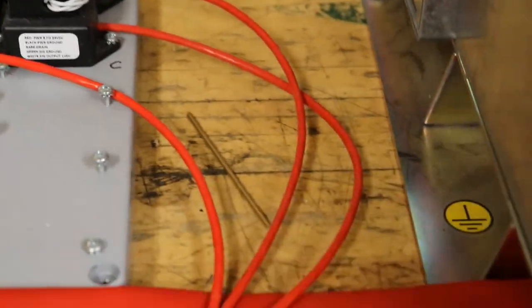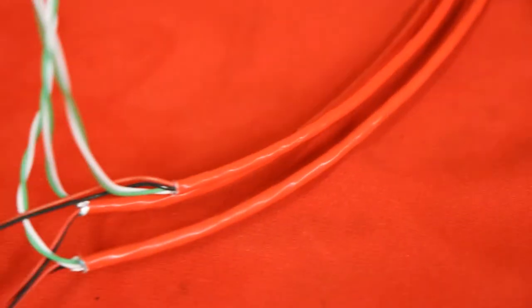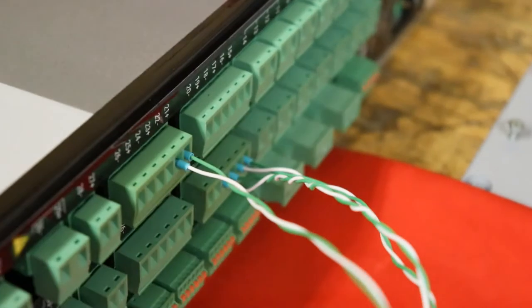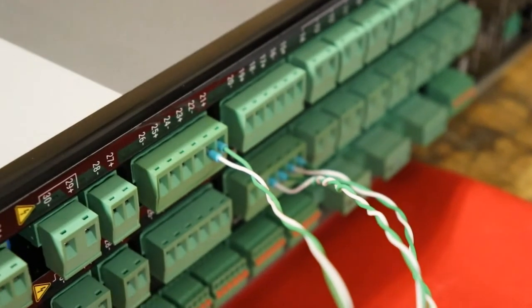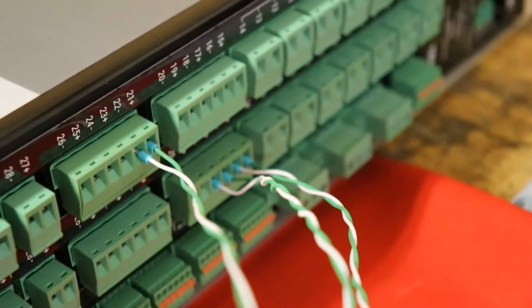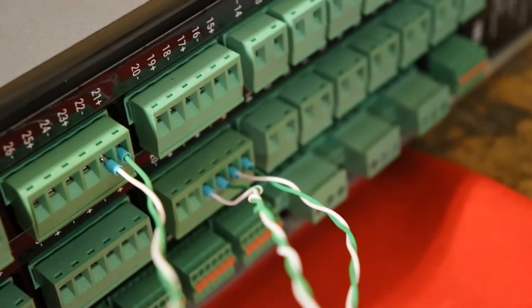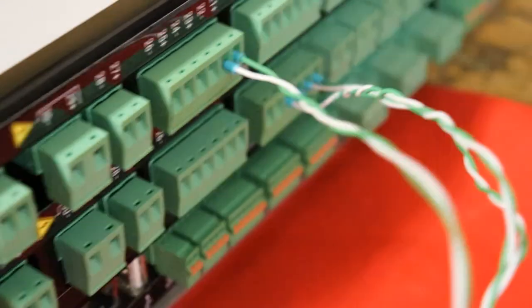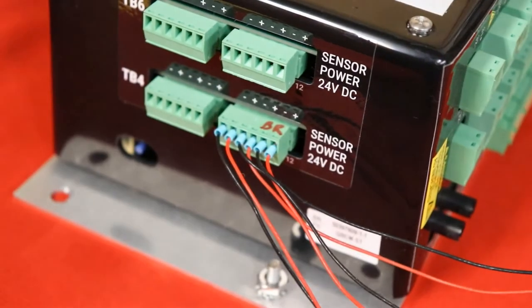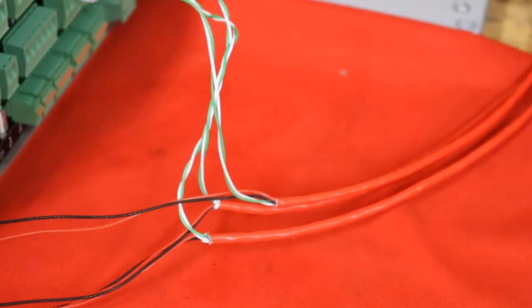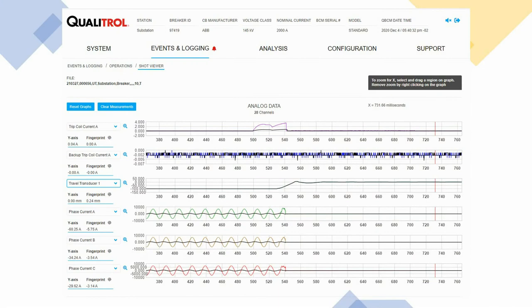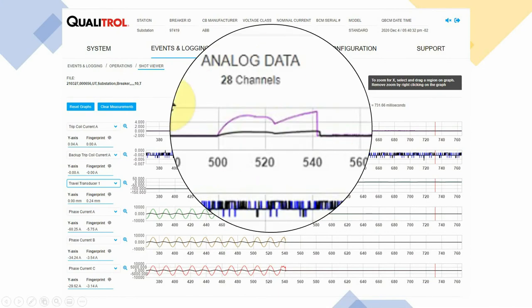The cable of the sensor includes all the wires for power supply as well as signal. The signal cables are wired to the terminals on the QBCM as shown here. The power supply to the sensor is also provided through QBCM as shown here, making the installation very easy and user-friendly.